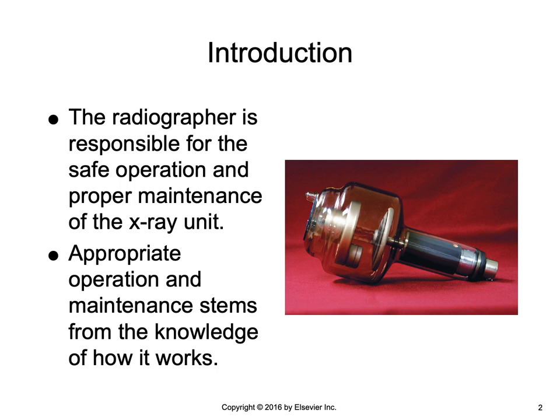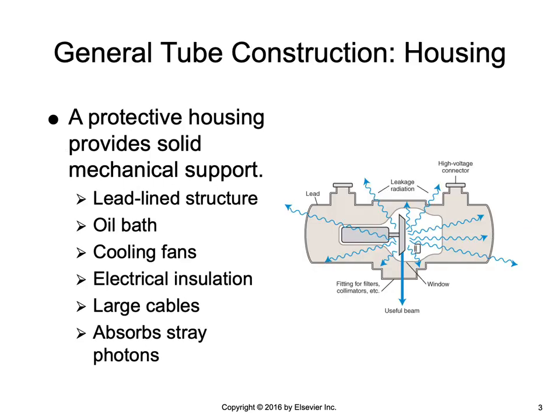This photograph shows a basic rotating anode x-ray tube. The x-ray tube is situated in a protective housing that provides solid, stable mechanical support. The housing is a lead-lined metal structure that also serves as an electric insulator and a thermal cushion for the tube itself. X-ray production is a rather inefficient process and much of the electrical energy that goes into it is converted to heat.